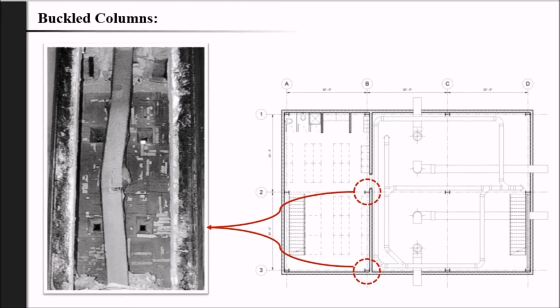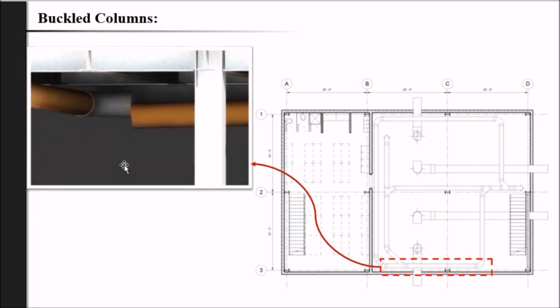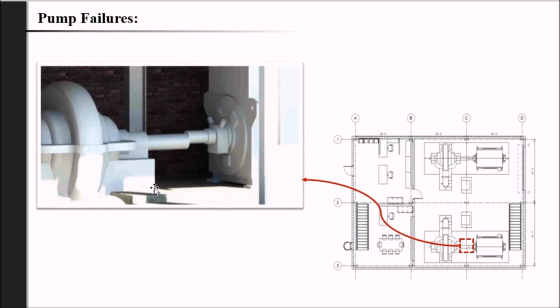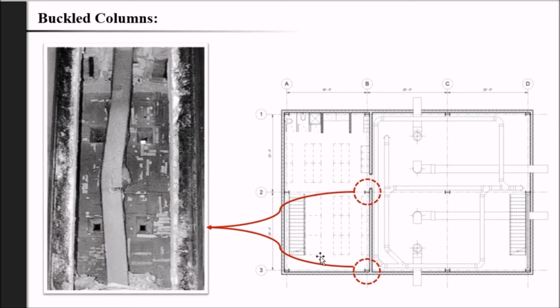But unfortunately, damages in the pump station building were not limited to just the mentioned damages inside the storage room. After the incident, the operating manager noticed this pipe, as you can see in this picture, and also this pump shaft on the ground floor, as you see here, were also broken. To realize the failure mechanism and the causal relationship between the fire inside the storage room and the damages to the equipment in the other parts of the building, we have to run the post-incident structural analysis using the finite element analysis software.